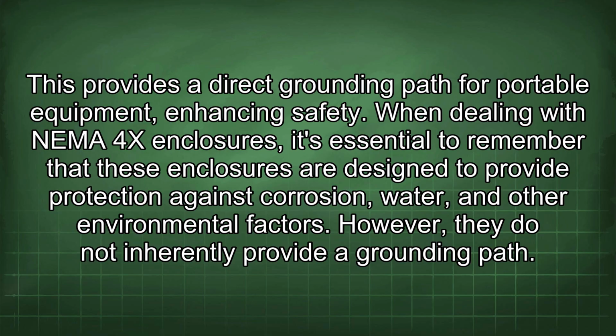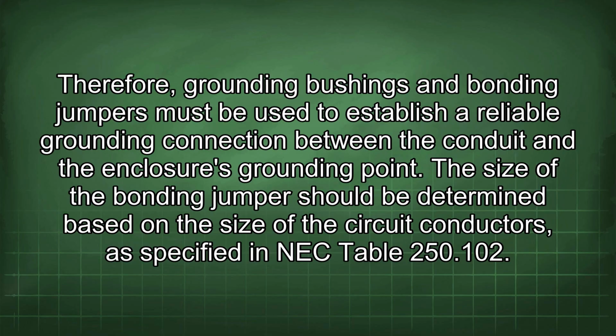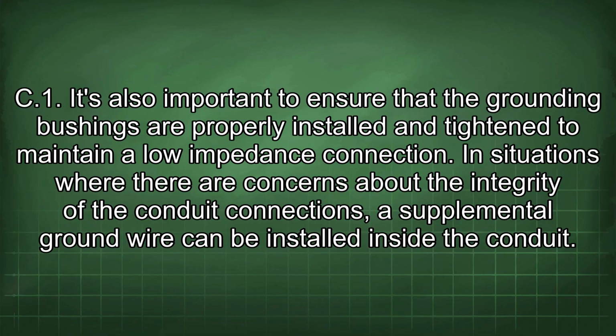When dealing with NEMA 4X enclosures, it's essential to remember that these enclosures are designed to provide protection against corrosion, water, and other environmental factors. However, they do not inherently provide a grounding path. Therefore, grounding bushings and bonding jumpers must be used to establish a reliable grounding connection between the conduit and the enclosure's grounding point. The size of the bonding jumper should be determined based on the size of the circuit conductors, as specified in NEC Table 250.102.